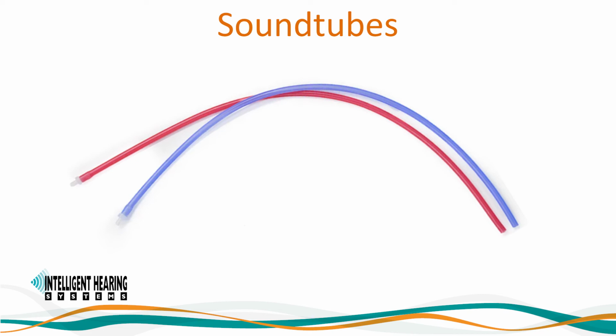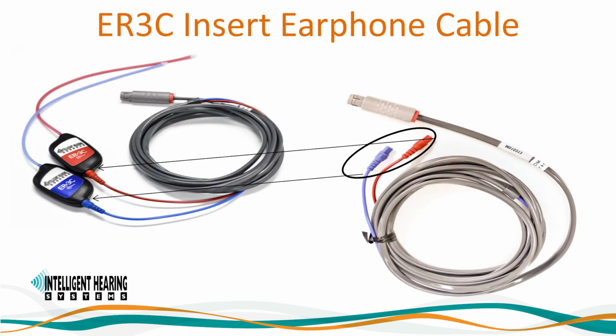A calibration check should be performed on-site immediately prior to use. When using the ER3C insert earphone, make sure that the red and blue quick disconnect cables are pushed in all the way into the black speaker boxes prior to testing. Carry out a listening check if no responses are seen or unusual waveforms are recorded.